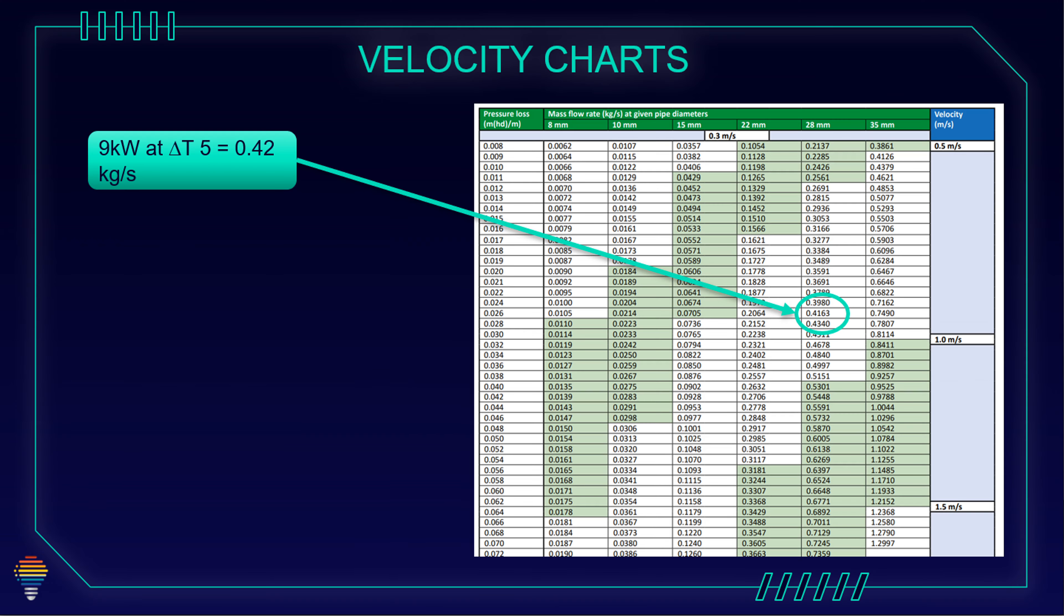For example, we have nine kilowatts for heat pump. As we explained in previous video, this nine kilowatts, if we have delta T of five degrees, our flow rate is 0.42 kilogram per second. If we go in our table, we can see that for velocity of one meter per second, our pipe for our nine kilowatts at delta T of five will be 28 millimeter.